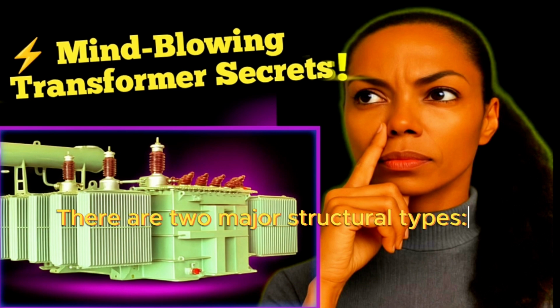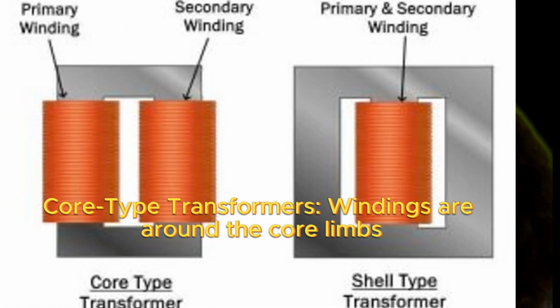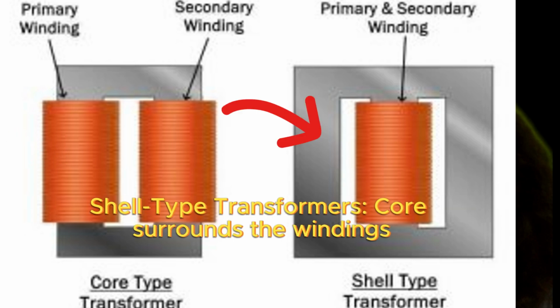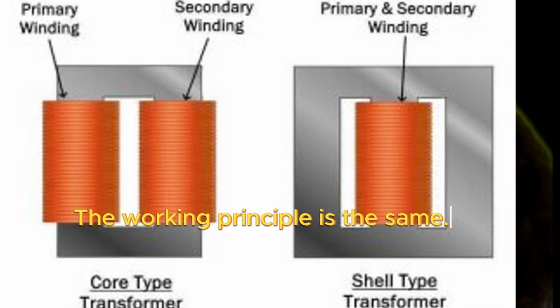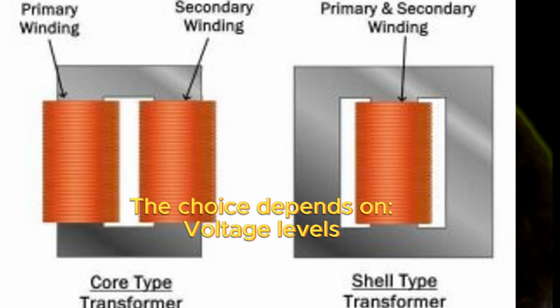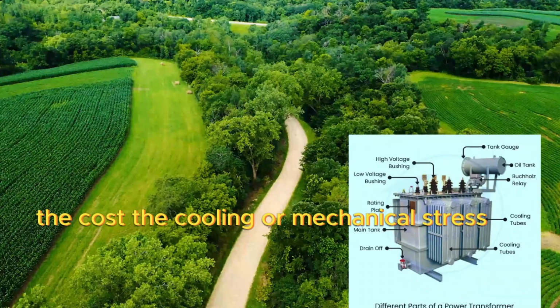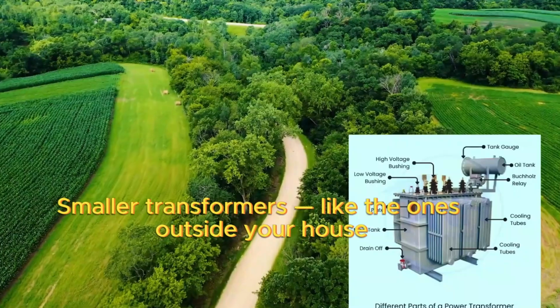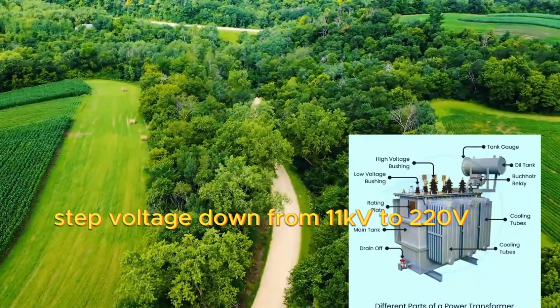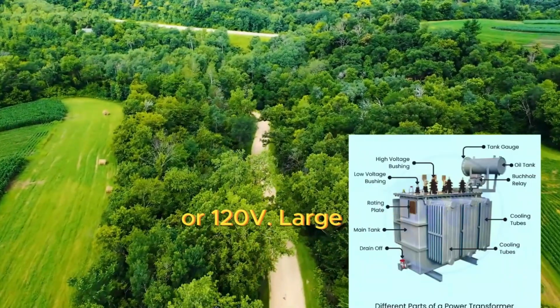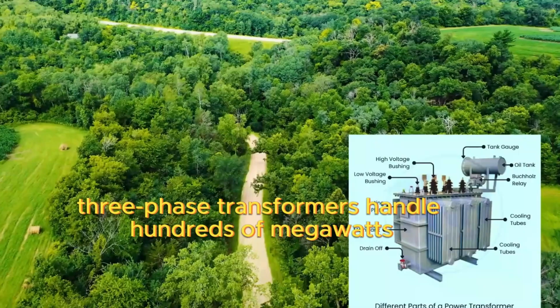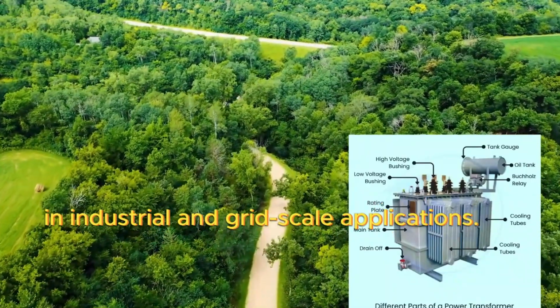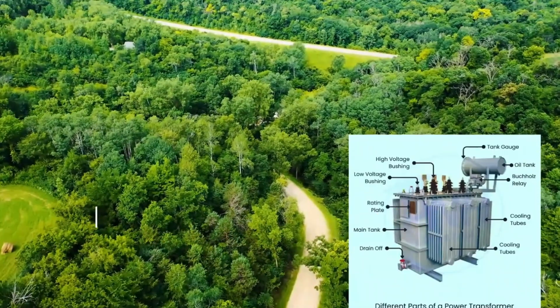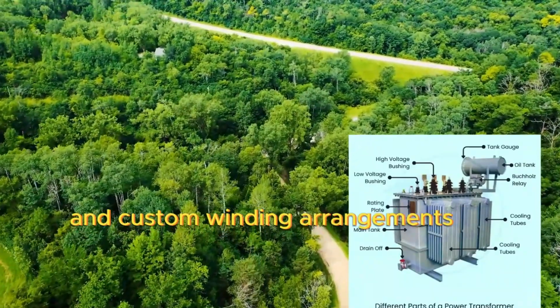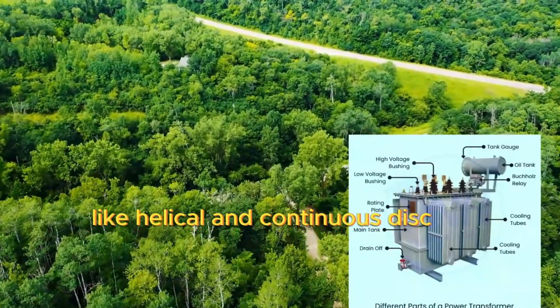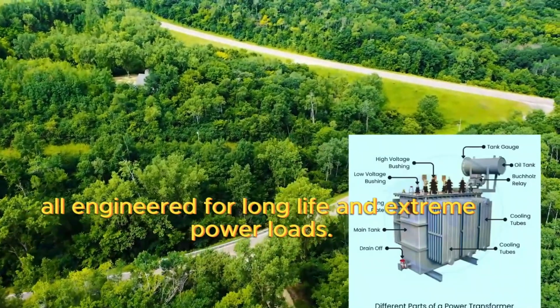Types of transformers. There are two major structural types. Core type transformer: windings are around the core limbs. Shell type transformer: the core surrounds the windings. The working principle is the same. The choice depends on the voltage level, the cost, the cooling, or mechanical stress. Smaller transformers, like the one outside your house, step voltage down from 11 kilovolts to 220 volts or 120 volts. Large three-phase transformers handle hundreds of megawatts in industrial and grid-scale applications. These use a star-delta connection, special paper insulation, and custom winding arrangements like helical and continuous disc, all engineered for long life and extreme power loads.